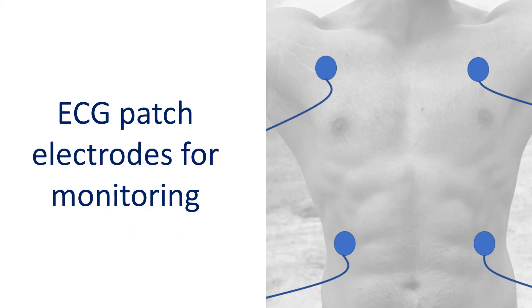While monitoring ECG in the ICU, the electrode wires usually kept on the limbs are attached to the parts of the body nearest to the limbs. This is to reduce the pickup of unwanted signals from the muscles during movement of limbs. Attachment to the body also avoids tethering of the person.